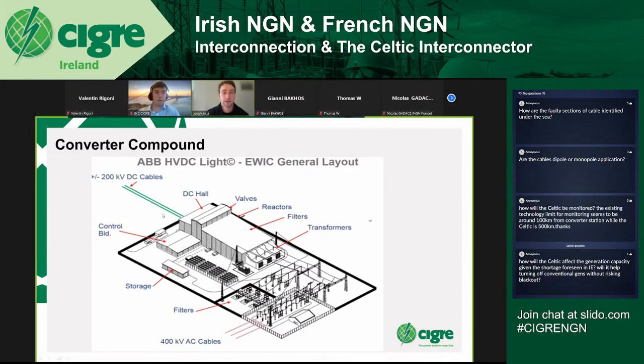You can see the DC cables come into this DC hall, where the terminations are. The valve hall is where the conversion, inversion, or rectifying takes place. VSCs have their own reactors and filters to filter out harmonics and provide compensation. Then there are standard AC transformers into an AC bay and out onto the transmission system. That's really it there, Connor, I'll take any questions at the end.